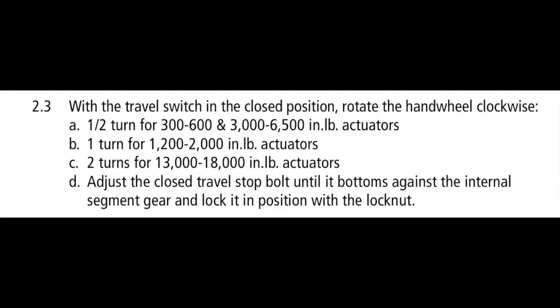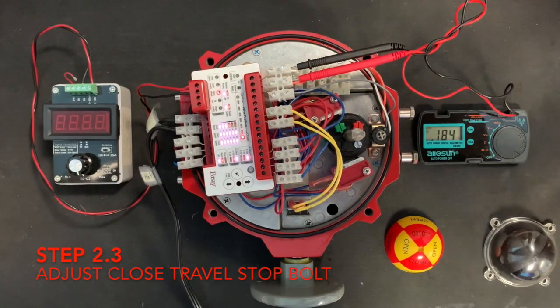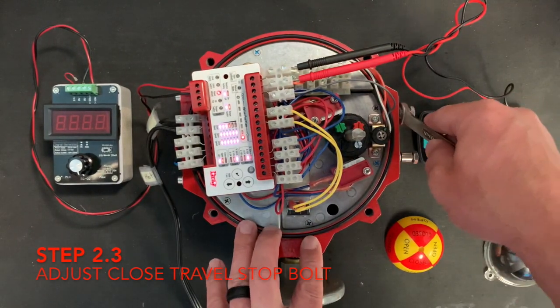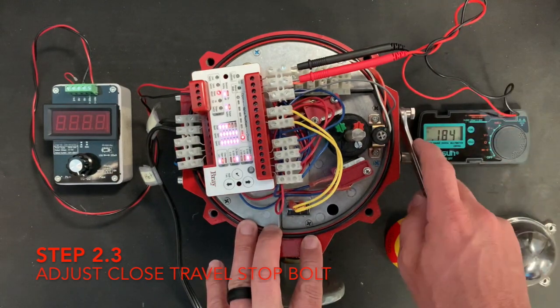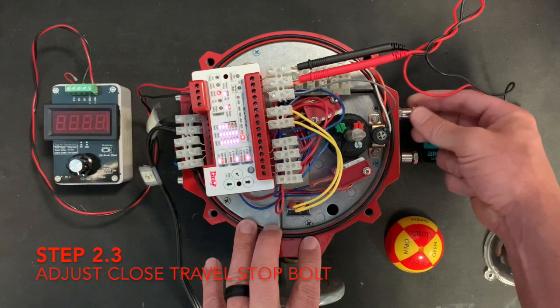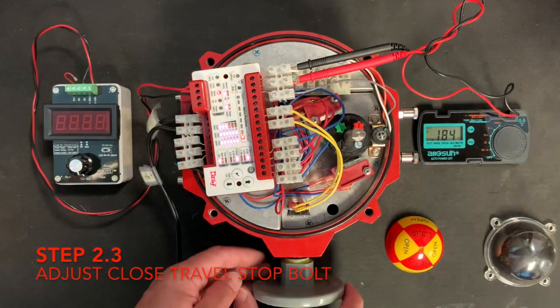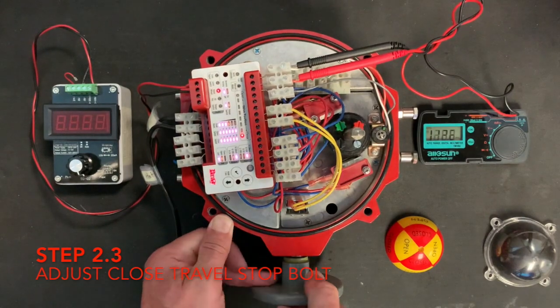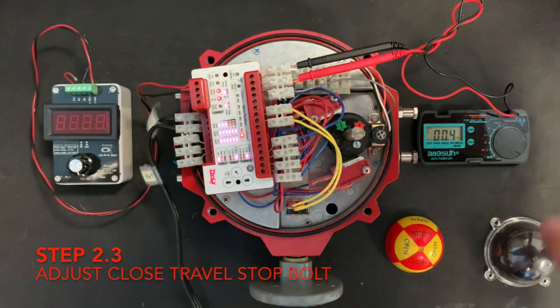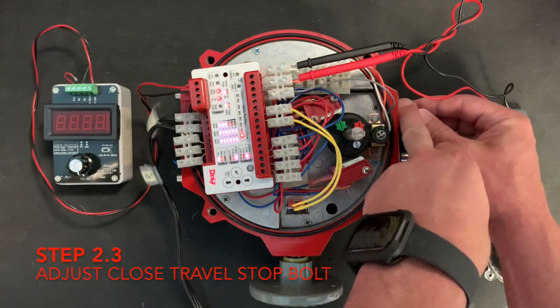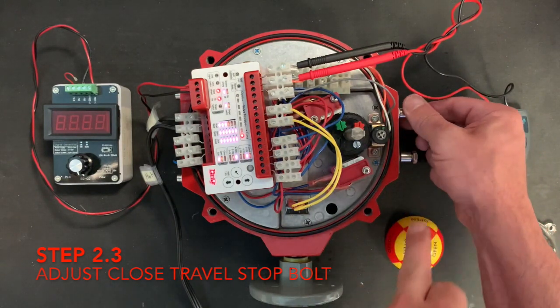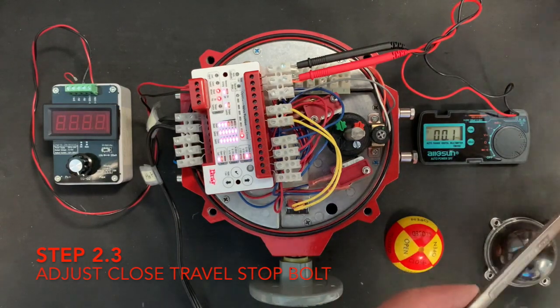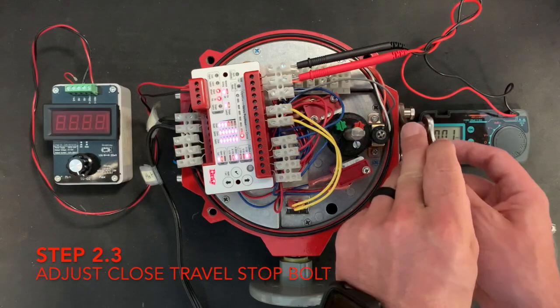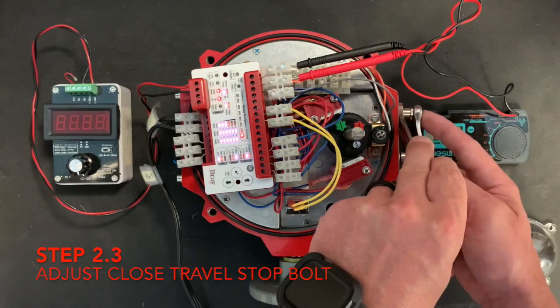With the travel switch in the closed position, rotate the hand wheel clockwise. This depends on the size: 1/2 turn for 300 to 600 inch-pound and 3,000 to 6,500 inch-pound actuators, 1 turn for 1,200 to 2,000 inch-pound actuators, and 2 turns for 13,000 to 18,000 inch-pound actuators. Adjust the closed travel stop bolt until it bottoms against the internal segment gear and lock it in position with the lock nut.